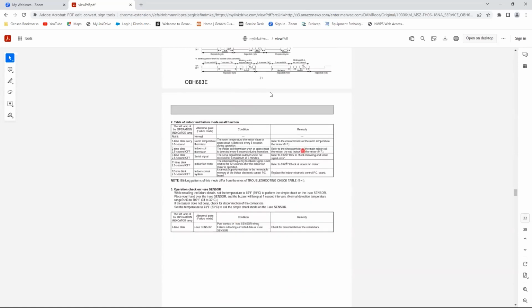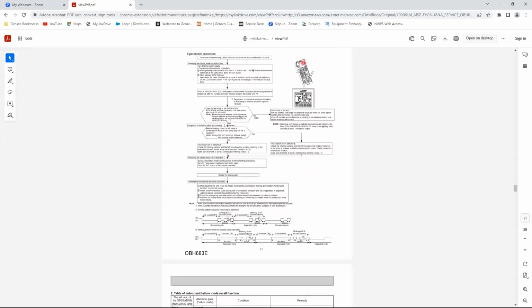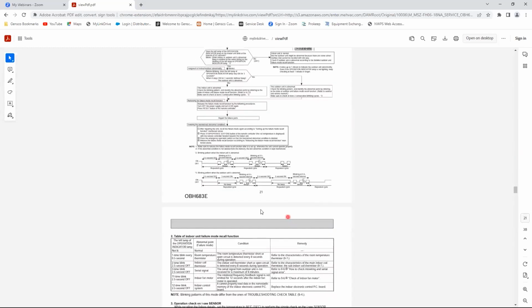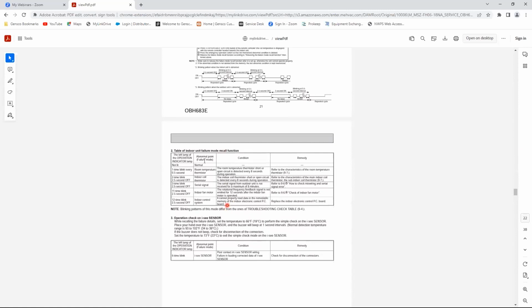Now, I will tell you, I call this the Vulcan death grip: you've got to push two buttons and then push the reset button with a pointy object, not too pointy. When you do failure recall mode, only use the table that says failure mode recall, because the error codes are different if it is a failure mode recall error or if it is an active error. An active error is when you walk in and the head is flashing at you, or you walk to the outdoor unit and the outdoor unit is flashing its lights at you, giving you an error code.